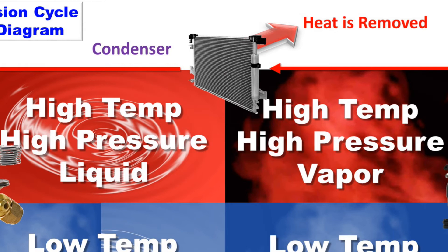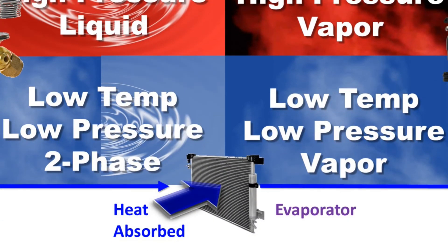The high pressure, high temperature upper half allows the refrigerant to become significantly hotter than ambient air, forcing heat transfer. The low temperature, low pressure half of the cycle allows the refrigerant to absorb heat from a source that is not as hot as the environment. The compressor does the work to raise the pressure and the expansion valve ensures that adequate pressure is retained for heat transfer.